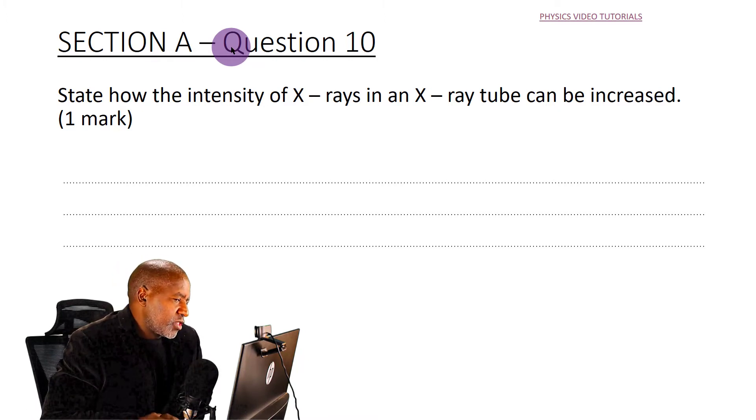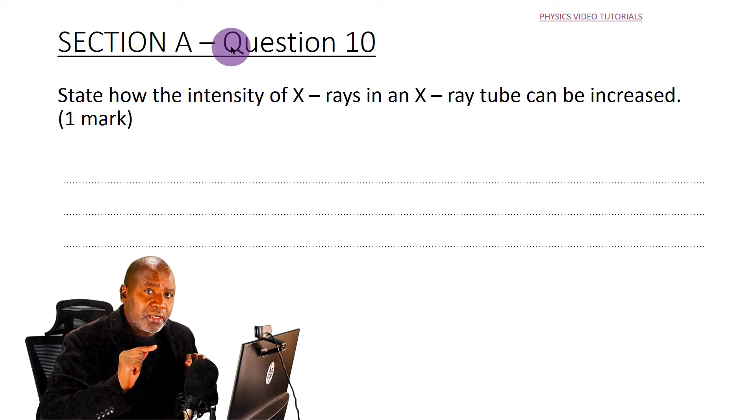This is a very direct question. And we increase the intensity of x-rays by increasing the current which flows through the heater of the cathode, or we increase the heater current.